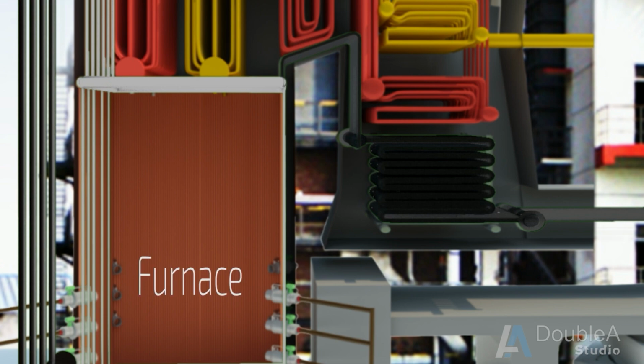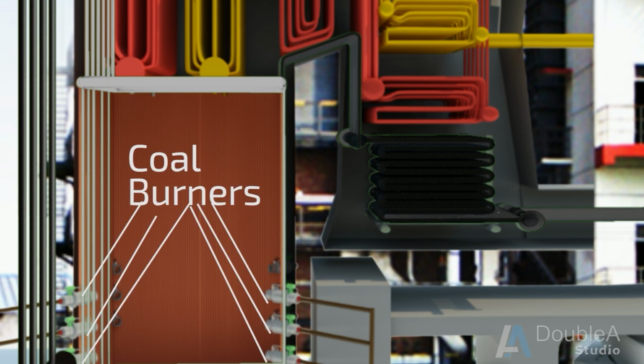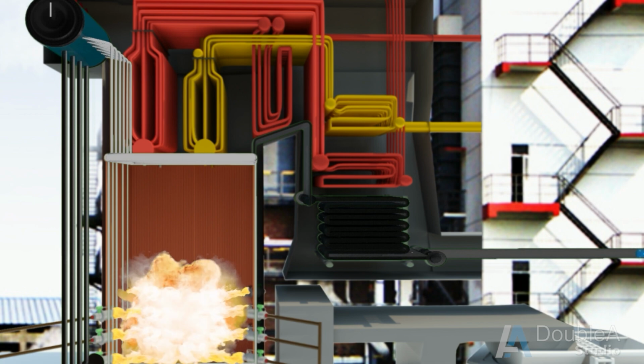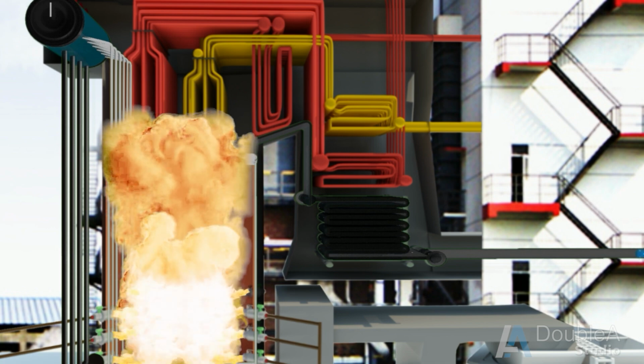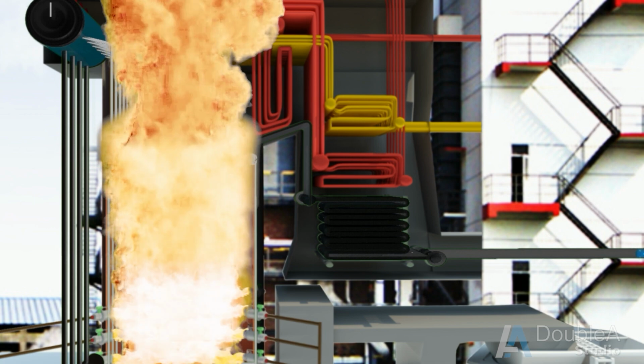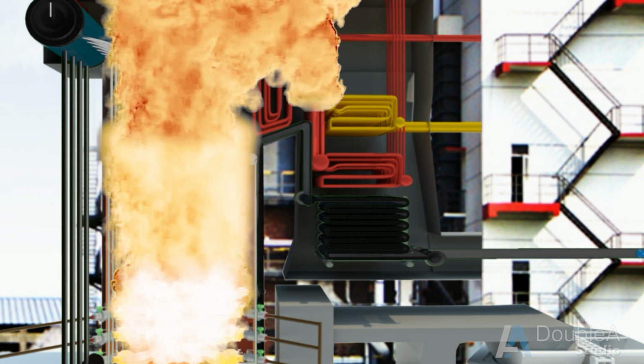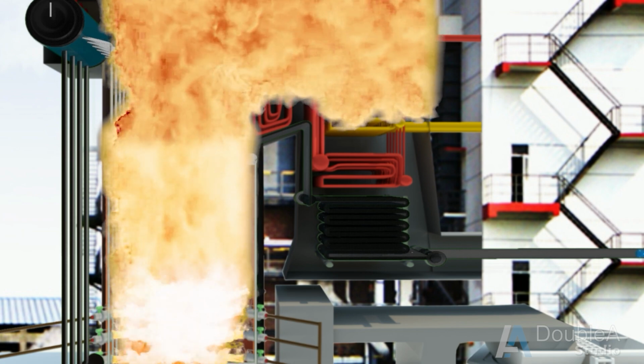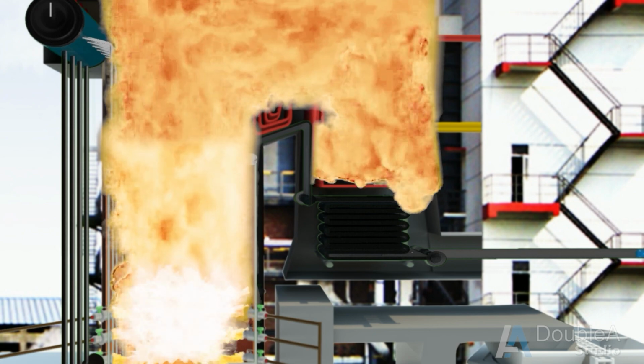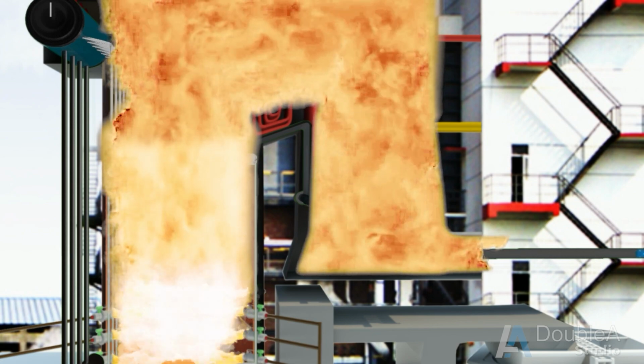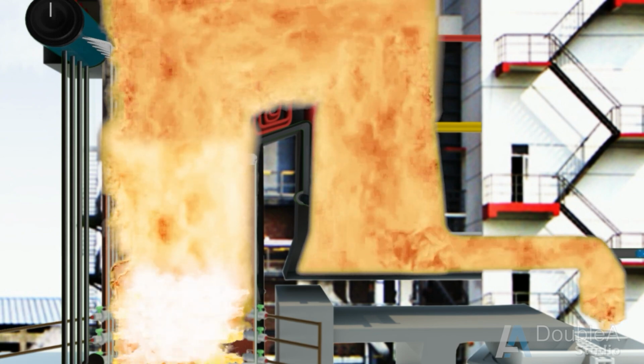First is the furnace. It is equipped with coal burners at all 4 corners, repeating at 3 or 4 levels. This arrangement is known as tangential firing. Powdered coal from the mill is discharged from the nozzle of the burners and is ignited. It produces an intense fireball which spreads out and fills the entire furnace area.